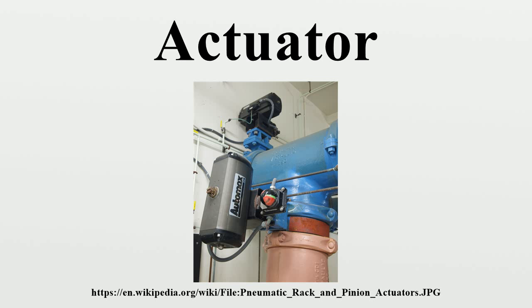Pneumatic. A pneumatic actuator converts energy formed by vacuum or compressed air at high pressure into either linear or rotary motion. Pneumatic energy is desirable for main engine controls because it can quickly respond in starting and stopping, as the power source does not need to be stored in reserve for operation. Pneumatic actuators enable large forces to be produced from relatively small pressure changes. These forces are often used with valves to move diaphragms to affect the flow of liquid through the valve.